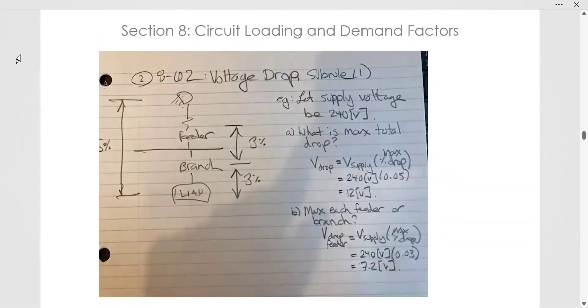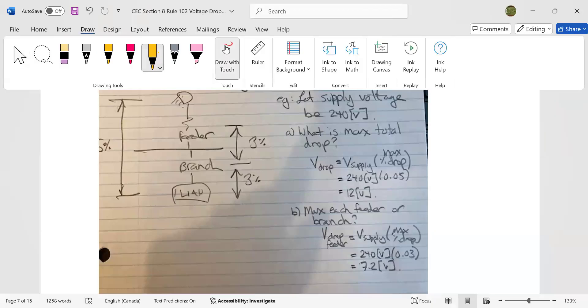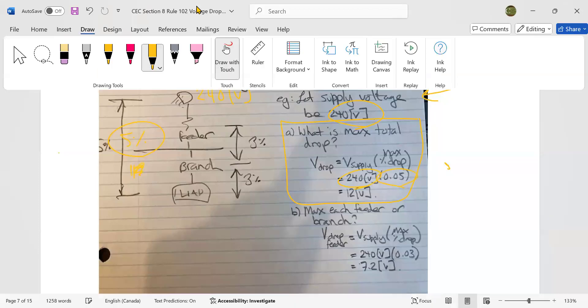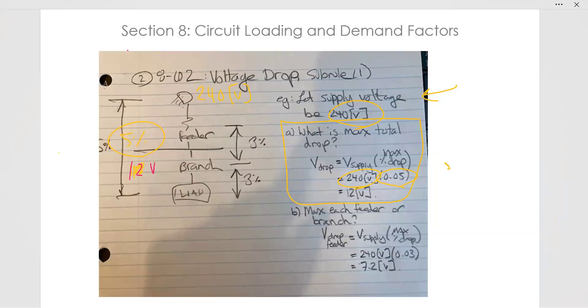Here's an example we can do about subrule one. So this is a voltage drop example for subrule one. So if the supply voltage is, this is a good question for any of the exams, so please study this. If the supply voltage is 240 volts, which means, here we go, we have 240 volts here, then what is the maximum total voltage drop that's allowed? Well, it is 5%. The maximum amount is 5% of that 240 volts. So it is simply 240 volts times 5%, which is 0.05 in a decimal form. So that is 12 volts. So the maximum amount that this can decrease across the conductor length is 12 volt drop.